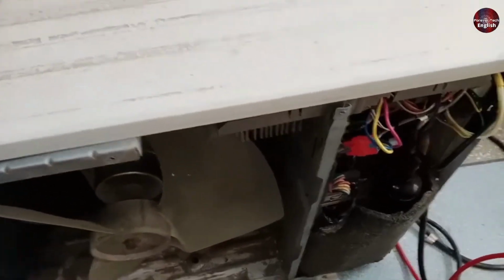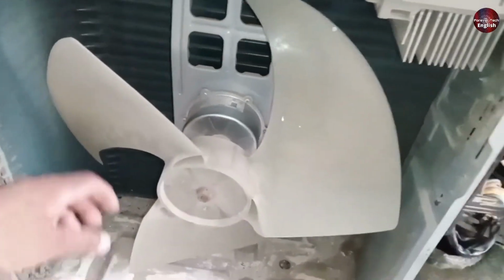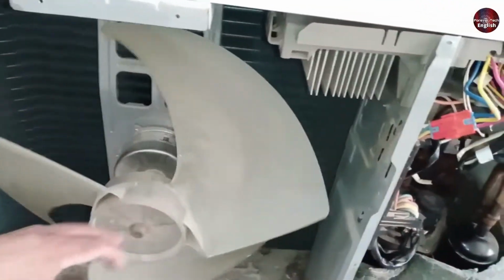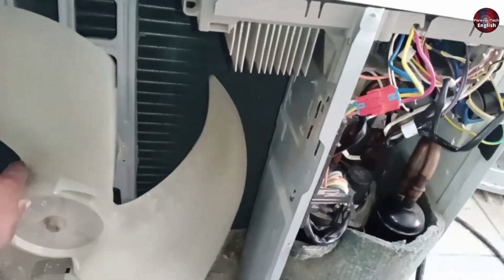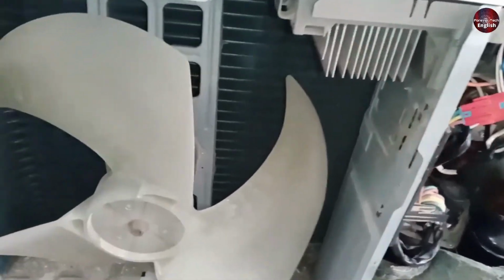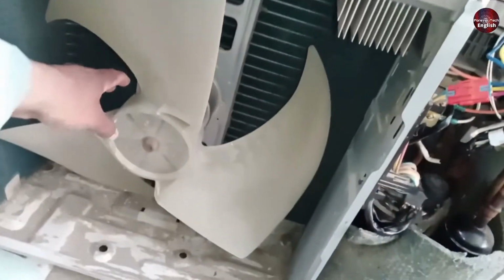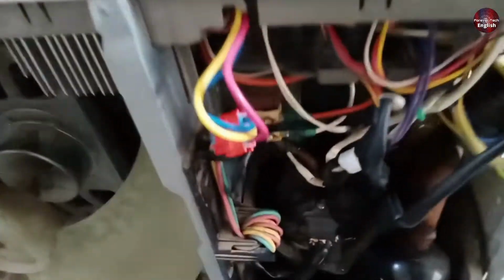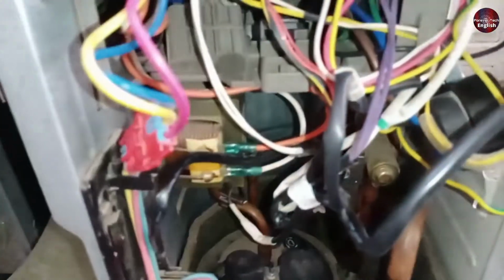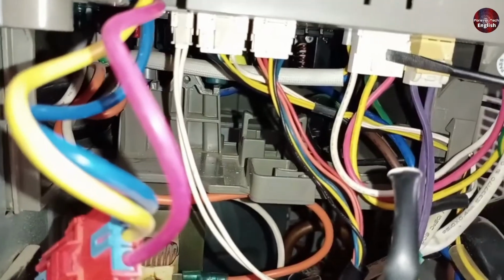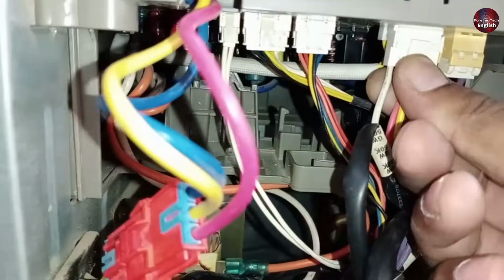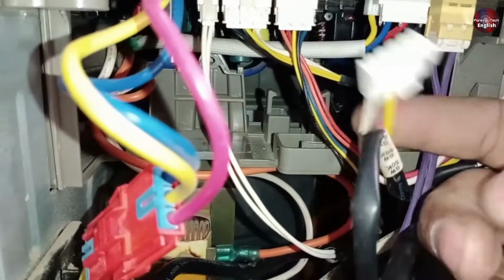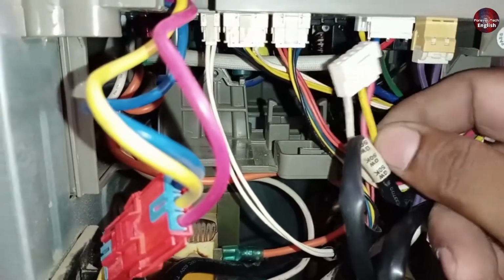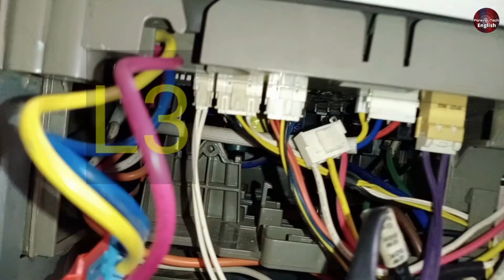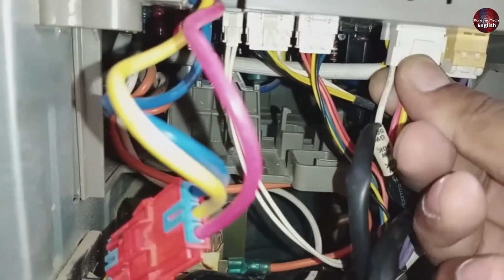If the fan motor in the outdoor unit becomes faulty for any reason or gets jammed, though right now this motor is working fine, if the motor jams or has difficulty rotating, it means that the motor is faulty and needs to be replaced. In addition, let me show you where the connector is located on the PCB. Look here, this connector is for the outdoor unit's DC fan motor. I've removed this connector, and it is installed here. If this connector becomes loose or disconnects for any reason, the L3 error code will show on your display. You can simply reinstall it to fix the problem.